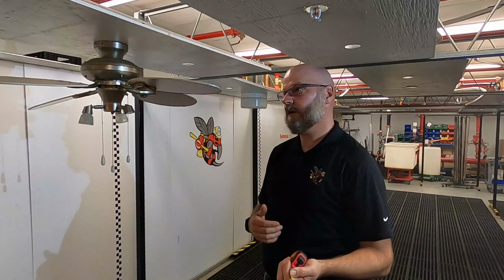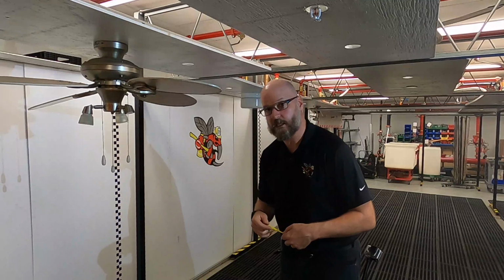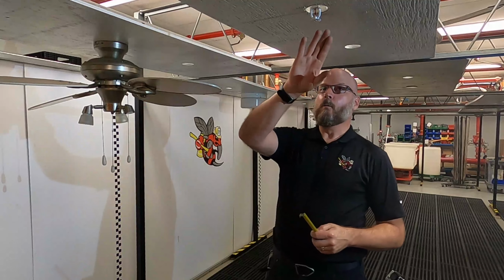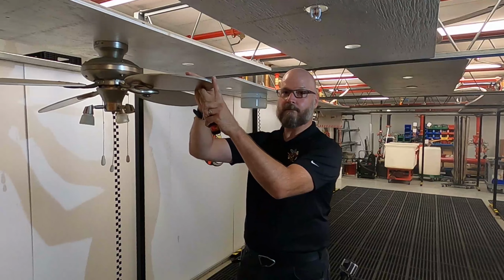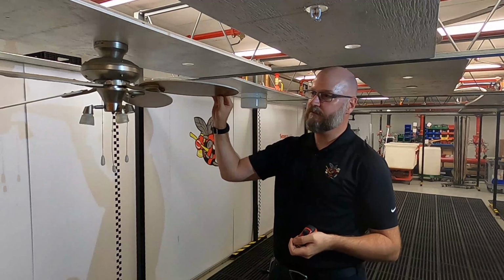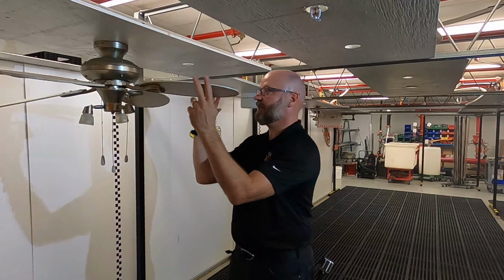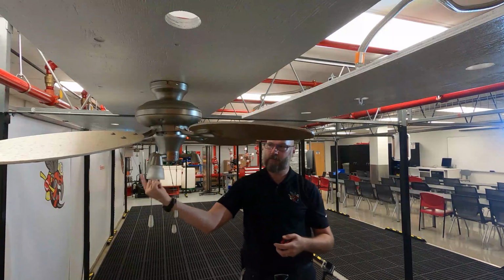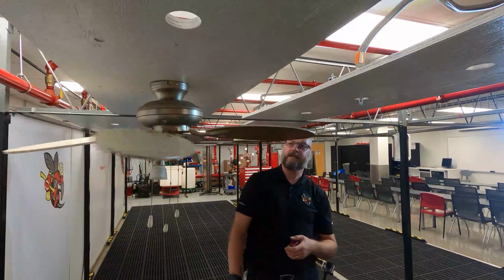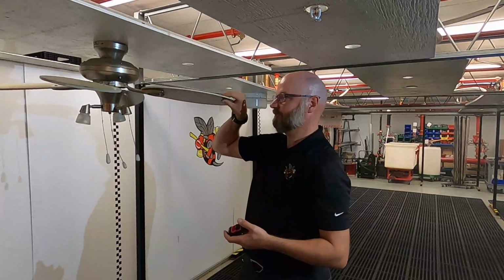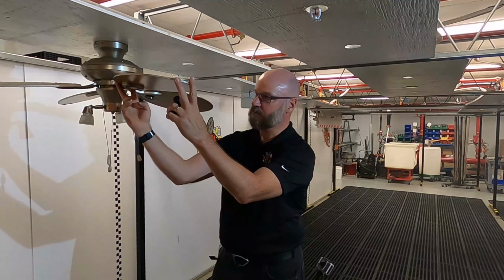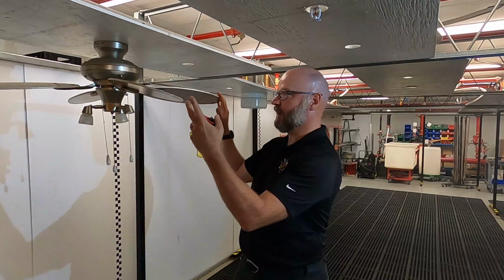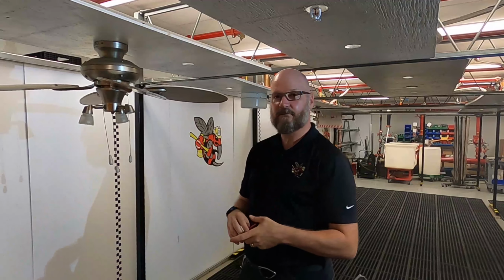Now that being said, there are special criteria for massive fans. High volume, low speed fans are covered differently up in chapter 20. But for this, we're doing residential sprinklers, talking about all things residential. We don't measure to the edge of the fan blade. The only time we would ever measure to the edge of the fan blade is if the fan blades themselves take up more than 50% of the area that they revolve within. So while it's spinning, you can think about the area here, all 4 blades would have to take up much more area to exceed that 50%.